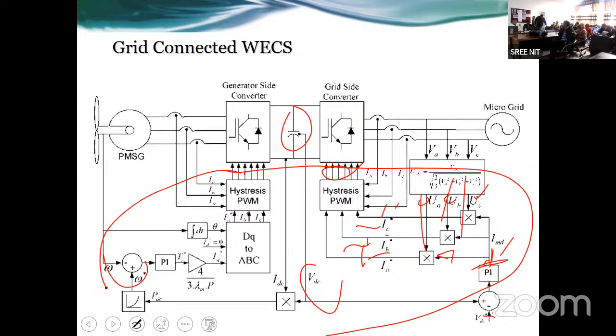Switching frequency means, if 10 kilohertz is the switching frequency, that means 1 by 10 into 10 to the power 3. It comes out to 10 to the power minus 4, within 100 microseconds. Within 100 microseconds, all these calculations, right from measurement to calculation and everything, must be done. Only then is your system going to work perfectly. Otherwise, the next switching sequence will come. So all the measurements, all the calculations, everything needs to be done within the same switching period. Otherwise, your control will be false.